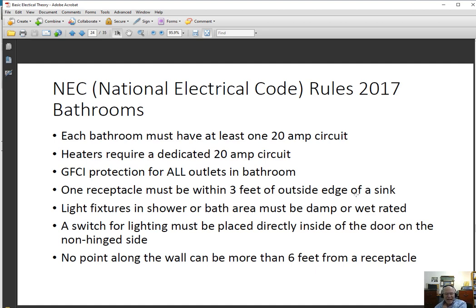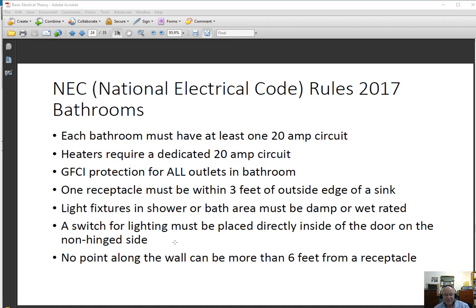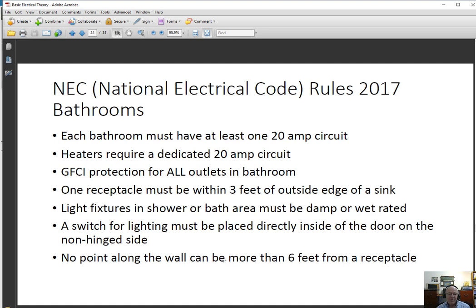There must be at least one receptacle within three feet of the outside edge of a sink. If you have dual sinks, you'd probably put that receptacle between them since it would then be within three feet of both. In every room in your house, you must be able to turn on lights by walking through the door — a switch for lighting must be placed directly inside the door on the non-hinged side, so you don't have to walk around the door to find the switch. The idea is that before you enter a room, you should have a way of turning lights on. That switch could go to a switched receptacle into which you plug a lamp. No point along any wall can be more than six feet from a receptacle, and that's true in the bathroom as well.